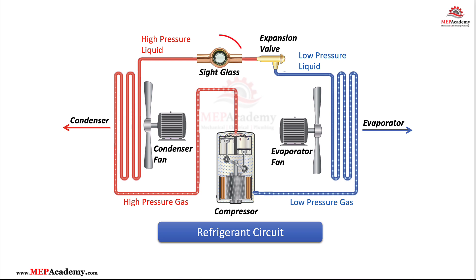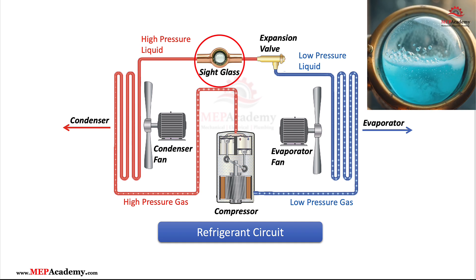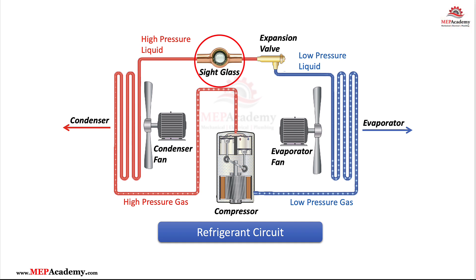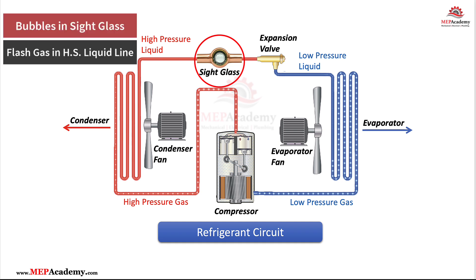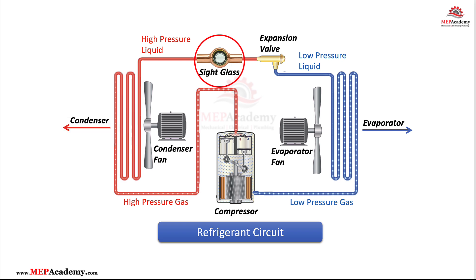Here on the liquid line, just before the expansion valve, you'll notice the sight glass. This is a critical inspection point for technicians. When the system is running properly, the sight glass should show a clear, full column of liquid refrigerant. If you see bubbles or foam here, it could indicate flash gas in the liquid line, often caused by a low refrigerant charge, loss of subcooling, or excessive heat gain in the line. Always remember: clear sight glass, healthy system.